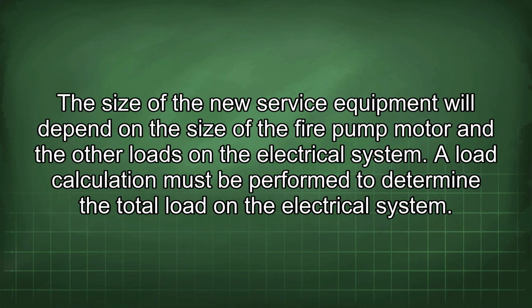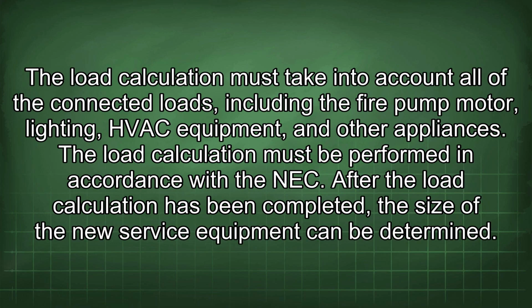The size of the new service equipment will depend on the size of the fire pump motor and the other loads on the electrical system. A load calculation must be performed to determine the total load on the electrical system. The load calculation must take into account all of the connected loads, including the fire pump motor, lighting, HVAC equipment, and other appliances. The load calculation must be performed in accordance with the NEC. After the load calculation has been completed, the size of the new service equipment can be determined.